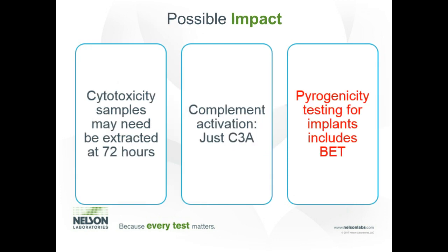Pyrogenicity has come into play, and they have a whole other ISO or FDA guidance document around pyrogenicity with the implants using the bacterial endotoxin test. If you are considered an implant, and there's also good webinars out there that can help go through this, you have to evaluate pyrogenicity, not just material-mediated pyrogenicity. You have to look at bacterial endotoxin, which is that LAL test that looks for specific pyrogen, which is that endotoxin. So don't think that just doing a material-mediated pyrogen will checkbox that requirement. If you're an implant, you have to not just look at material-mediated pyrogen, but you also have to look at bacterial endotoxin.